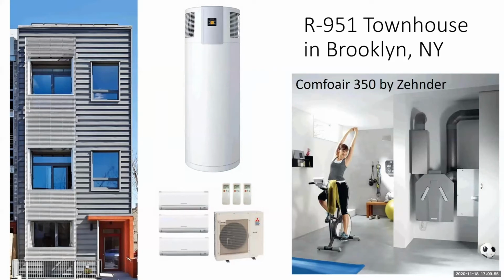I'm going to show you cold climate appropriate heat pumps for water heating that go outside too. But I wanted to immediately introduce what I think is the best practice: get an affordable, factory-integrated heat pump water heater tank, plug it into the wall, and use it inside the apartment, house, or residence. Use heat from a cold climate specialized heat pump, ones that go down to -20 or -30 Fahrenheit while still in heat pump mode, without needing electric resistance to perform at those temperatures.